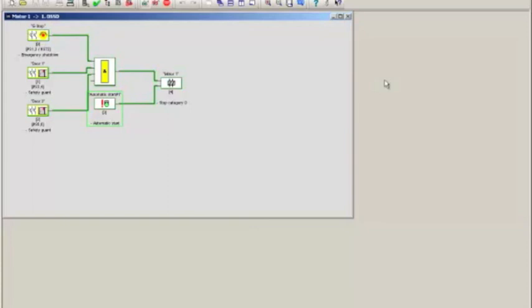So, let's open the door. I open the door and the motor immediately shuts down and when I close the door, the system auto-restarts just as we wanted to have it. So, we can combine the functionality of an auto-restart and a reset-restart very easily into one safe output. Something that in conventional hard-wired technology will require at least two safety relays.